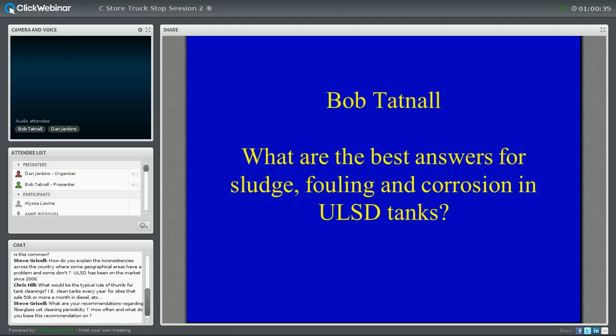Okay. Well, having worked with fiberglass a lot for DuPont, I would tell you I get scared at anybody going into a fiberglass tank to clean it, especially with metal implements. Fiberglass tanks depend on that thin resin-rich layer on the inside to be the liquid containment, and everything else is structural material to hold it together. So if you go in and damage that inner 32nd of an inch, say, layer of resin-rich material, you have just defined when the tank's going to start propagating a leak. And when you're going to discover the leak is sometime after that.